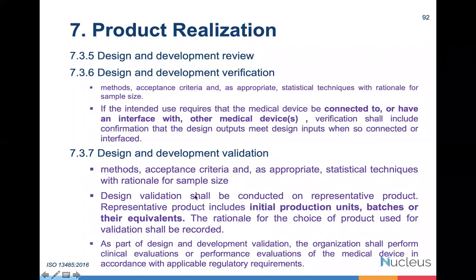And this is design and development validation. There is a mandatory requirement. As part of design and development validation, your company must perform clinical evaluation or performance evaluation. There are two options we have in front of us. Again, it depends on applicable regulatory requirements.